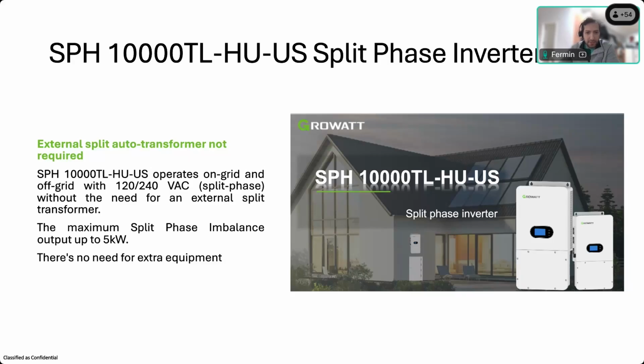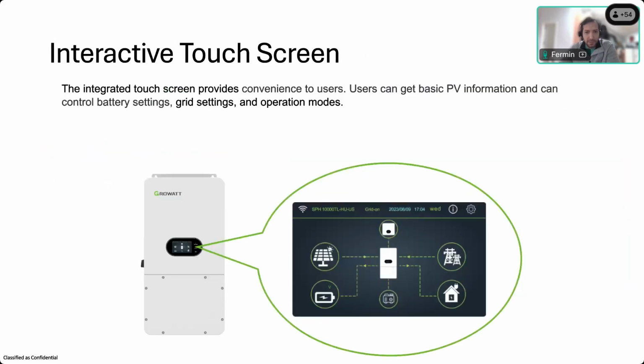In terms of the features overview, compared to the MIN inverter, this SPH inverter is able to provide a 120/240 volt split phase output. Therefore, you don't need to install an external device or a split phase transformer for this purpose. It allows 100% imbalance in between lines, meaning that you can output 5 kilowatts line to neutral, and then 0 on the other line. As I mentioned before, it comes with this interactive touchscreen, which allows you to see the real-time status of the system, faults, warnings, adjust settings, and do commissioning.